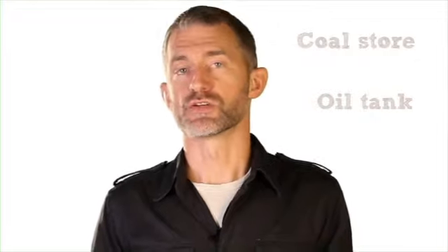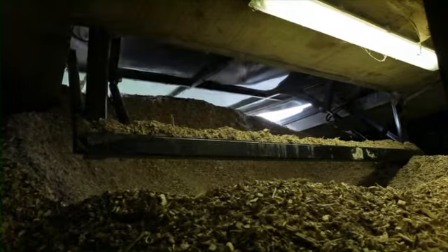In these situations, you'll need to investigate the potential to use the existing boiler room to house the biomass boiler. The space needed for a biomass boiler is not significantly different to coal or oil boilers, so in many cases this will be feasible. Although substantially more space will be required if you're replacing a gas boiler system. If your existing boiler is coal or oil, you'll also already have a coal store or oil tank, which may be a suitable location for the wood fuel store. It's likely to have to be enlarged, as wood chip takes up more space than either of these fuel types.